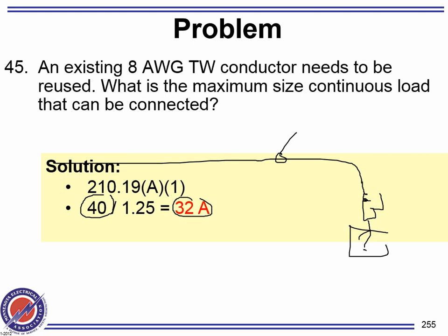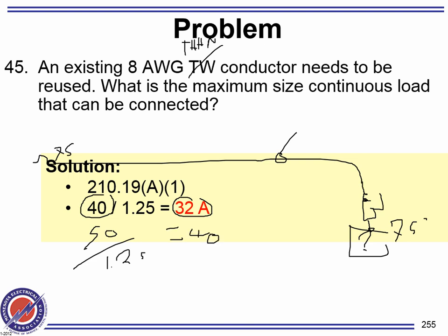Now look at that. This is THHN now. The lugs of this machine are rated for 75. I'm telling you, the lugs are rated for 75 here, and the breaker on this side is rated for 75. How much current can number 8 give me? Now where do you go? You're going to go to 75. Can you guys find 75? Under 75, how much can number 8 give you? 55 or 50? Do me a favor, divide this by 1.25. 40. Now you can get 40 amps. By the way, dividing by 1.25 is like multiplying by 0.8. So when you say multiply by 0.8 or divide by 1.25, it's the same. Do you see how it's different based on the installation and the lugs, not just the installation? I have to tell you something about the lugs. If I say it's also a motor and the lugs on both ends are rated for 75, then you go 75.